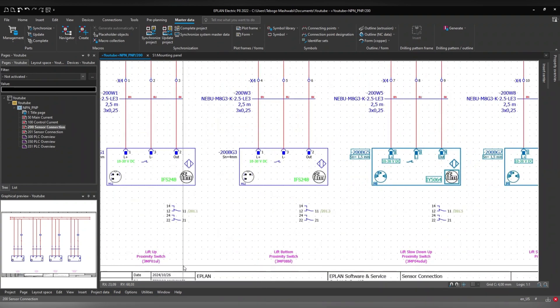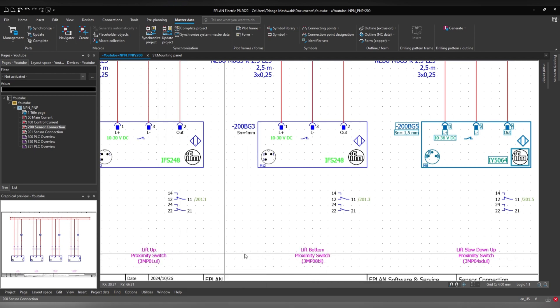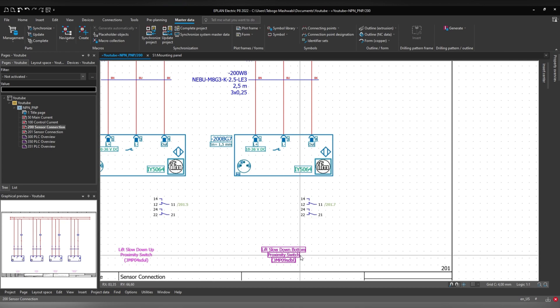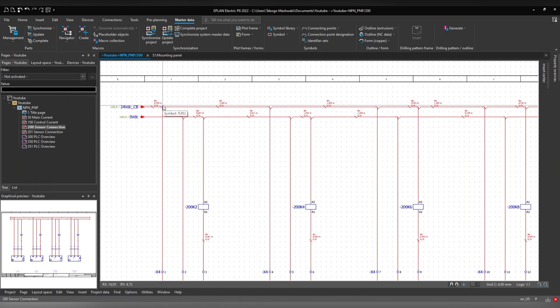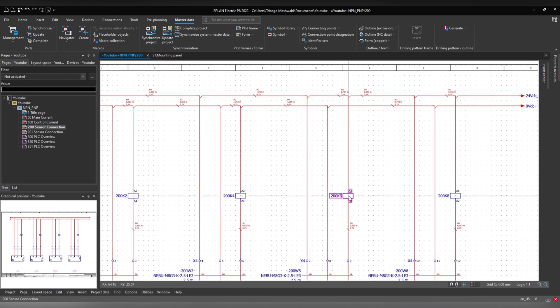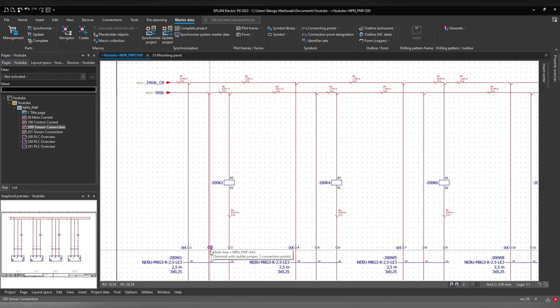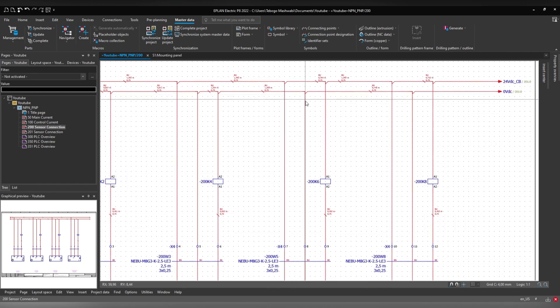I named them 'lift up' and 'lift bottom' — basically the lift at the ground floor and at the first floor. As the lift approaches the first floor we need to slow it down, and as it goes toward the ground floor we slow it down too. We use those 2 PNP sensors and 2 NPN sensors for that. You can see the 24 volts connected to terminals and to the relay loads. The zero volt connects to X2 terminals and to the relay coils, reflecting the NPN and PNP connection differences.